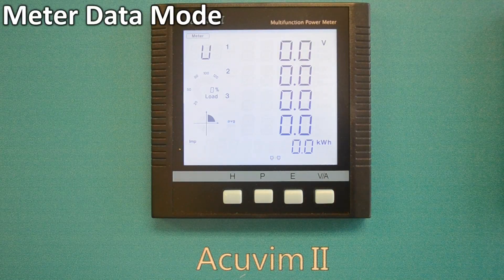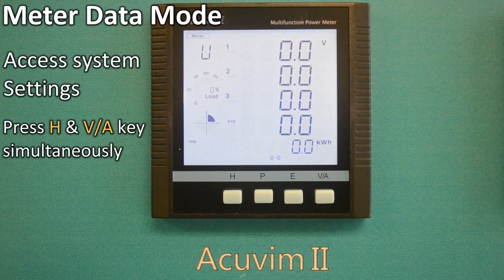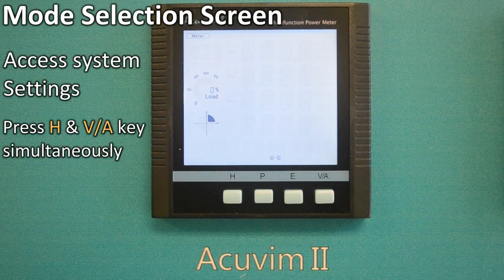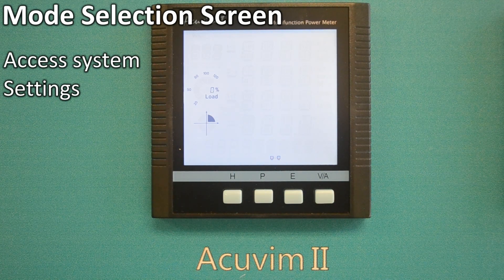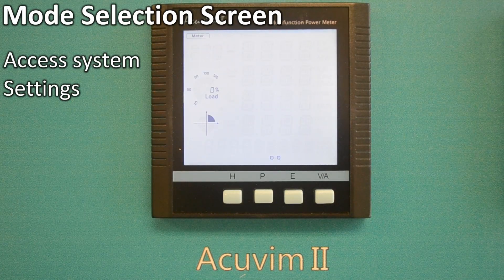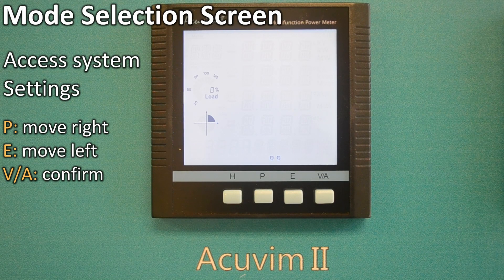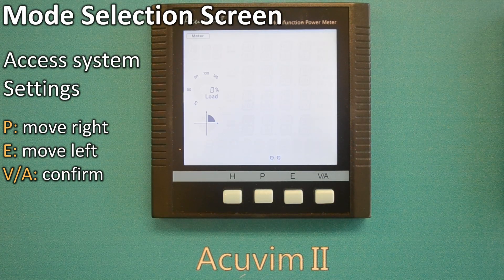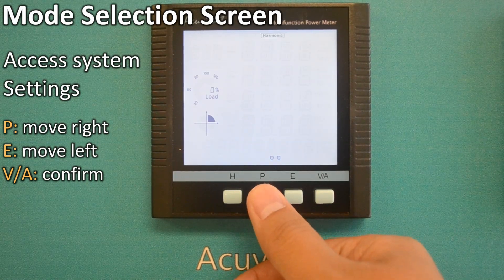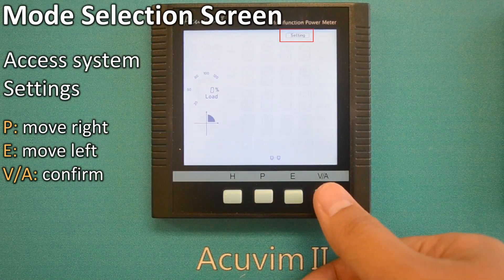Let's begin in the meter data mode. Press the H and VA keys simultaneously and the display will become blank, indicating you have entered the mode selection screen. The meter icon will now be flashing at the top of the screen. In the mode selection screen, the P and E keys are used for navigation. Press P to move right until the setting icon is selected, then press VA to confirm.